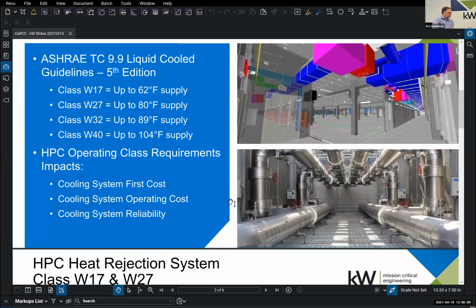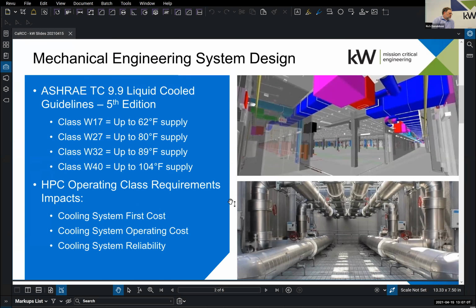Basically for liquid cooling, it breaks down into 4 different classes. ASHRAE recently, with the publication of their TC 9.9 guidelines, changed these classes up a little bit. You may have known them previously as W1, W2, W3, W4. Now they've changed it to W17 if you're supplying water up to 62 degrees to your high performance compute load, W27 if you're up to 80 degrees, W32 for 89 degrees, and W40 for 104 degrees. These are the Celsius, and these are the Fahrenheit conversions. ASHRAE is still doing their best to get us engineers used to this metric system, which is still an ongoing effort. How does the HPC operating class requirements impact you as a user?